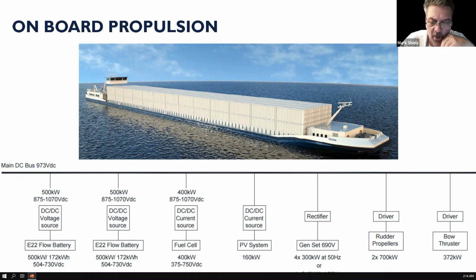They're designed to run for about 15,000 hours. On the fuel cell side itself, again there's no moving parts, only an air filter to worry about. The fuel cell will last 10,000 hours as well before we do some part replacement. But there's no oil change, oil filter, levels, or anything like that to be considered at all.